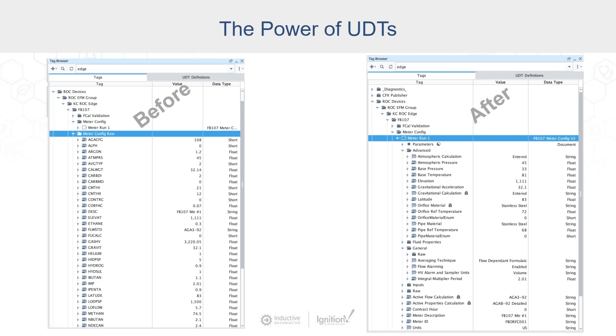Somebody asked: what's the best way to handle history and alarming when using UDTs? Within Ignition, you can define history and alarms on the definitions and all your instances will just inherit those properties. Those can all be parameterized — you could pass in parameters for which database you want the history going to, which alarm journal you want to log data to, what custom set points are going to be. In an MQTT architecture, you can certainly go deeper into where history and alarms get defined, whether that's at the edge of the network or centrally.